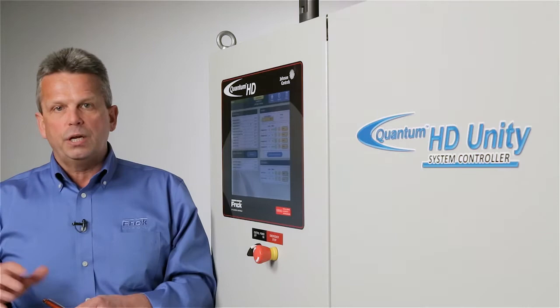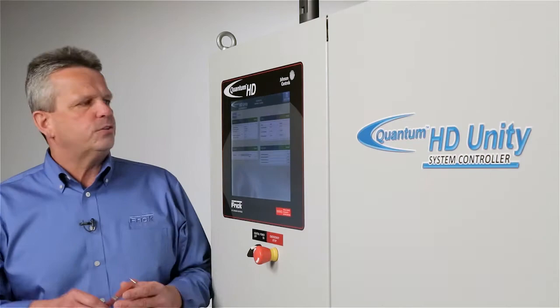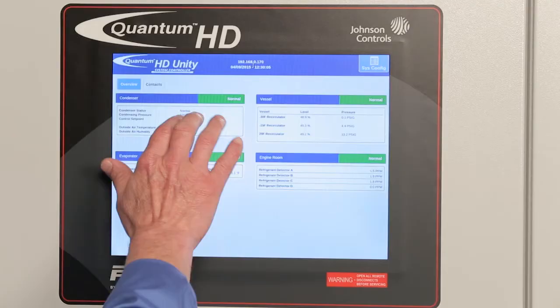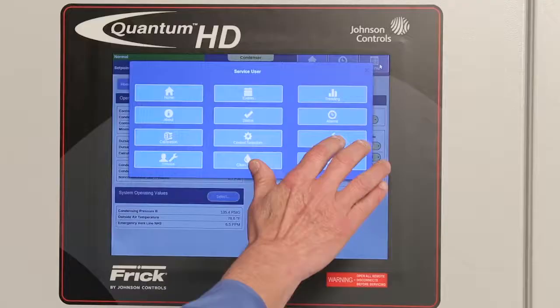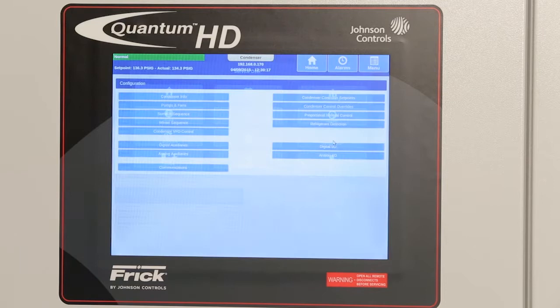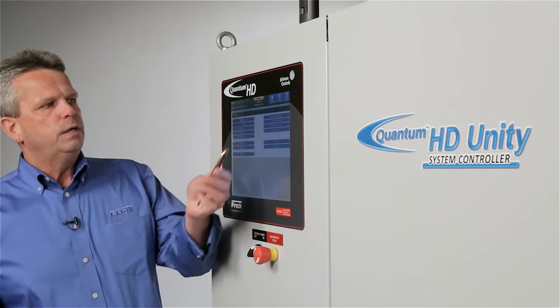Let's move on to condenser control. To access condenser control, from the system overview screen you simply touch anywhere in the condenser area and you see the home screen for the condenser control. Looking at the configuration menu, you have condenser information, pumps and fan configuration, summer sequence, winter sequence, condenser VFD control, condenser control set points, condenser control overrides, proportional integral control, and refrigerant detection. All these items get configured at startup of the system.